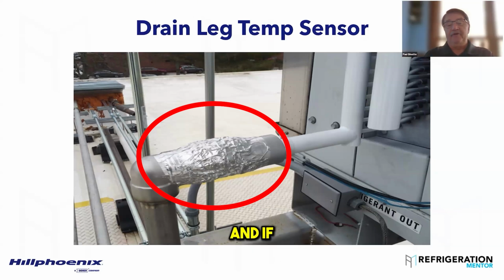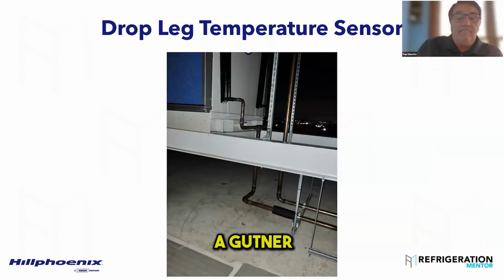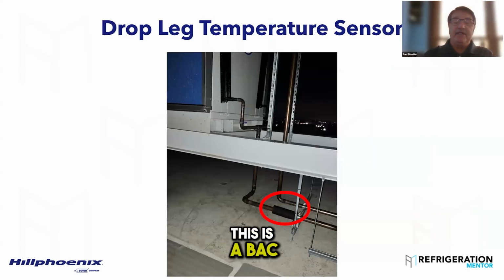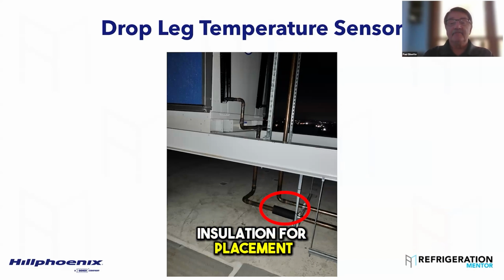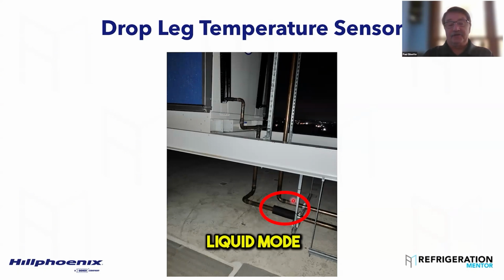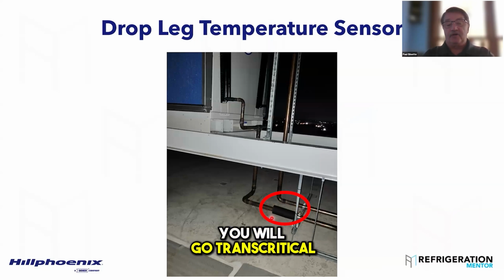Very important. And if you have a double condenser, like a BAC or a Guntner, this is a BAC. This is not the pipe. That black insulation down there at the bottom is not the proper selection for placement. It's all fine and dandy when you're in liquid mode and you're subcritical, but when you go transcritical, and even on an adiabatic condenser, you will go transcritical. That is going to cause you a lot of heartache.